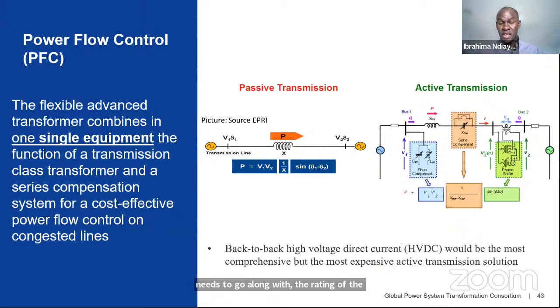The way to actively change voltage today is either boosting it at one end by adding shunt compensation, or at the other end by adding shunt reactors. But the most common methods for active power control, as we've heard, are phase shifters or series compensation. Series compensation is also well known for very long lines, but it has never been proven cost effective for shorter lines.